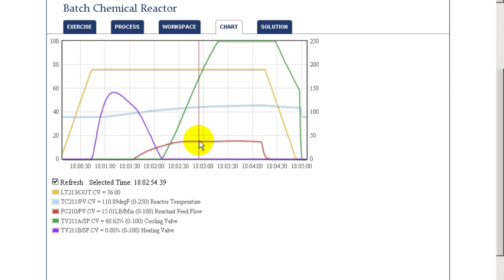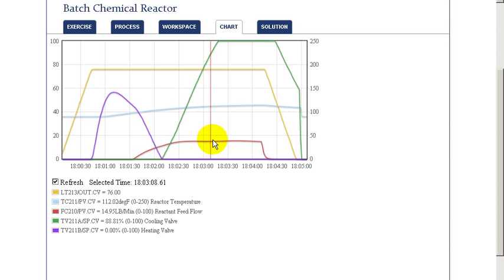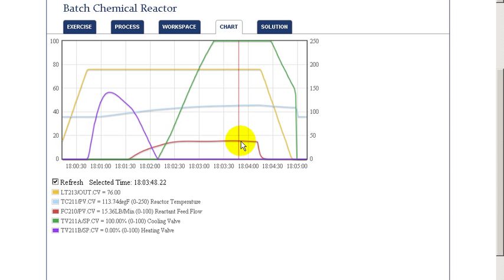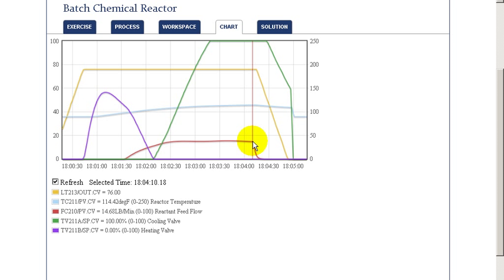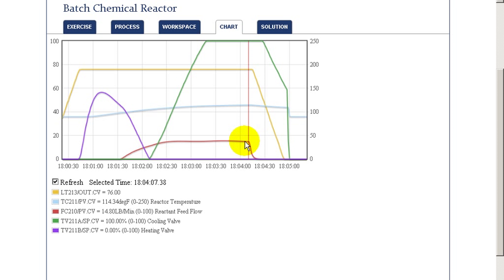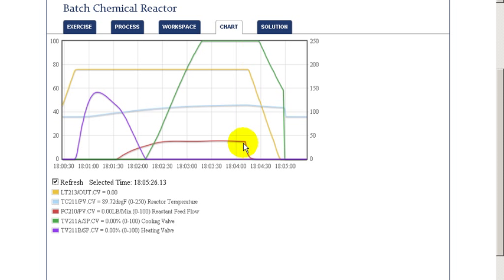So throughout the entire batch, then, the flow is limited to just a little over 15 to keep from exceeding our constraint limit. So the constraint, in this case, was very active throughout the batch and allowed the maximum to be put through without exceeding the constraint on the vessel.